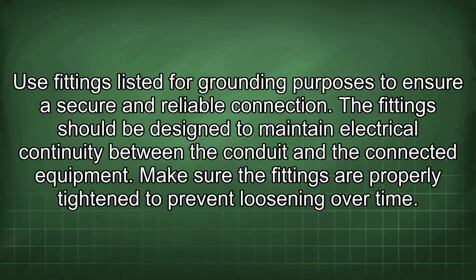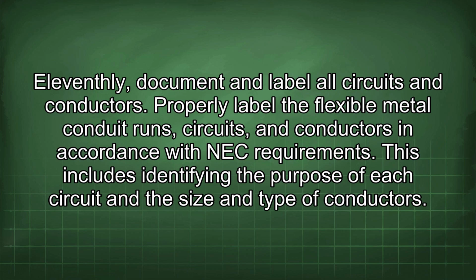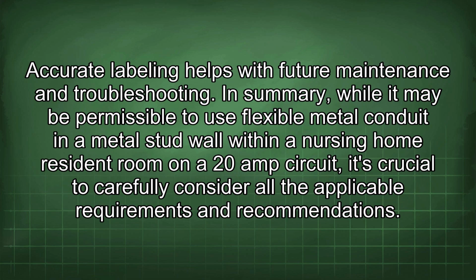Make sure the fittings are properly tightened to prevent loosening over time. Eleventhly, document and label all circuits and conductors. Properly label the flexible metal conduit runs, circuits, and conductors in accordance with NEC requirements. This includes identifying the purpose of each circuit and the size and type of conductors. Accurate labeling helps with future maintenance and troubleshooting.